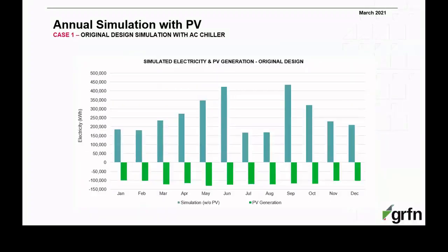If we compare the energy consumption versus the PV generation, we can see that, yes, the PV can generate a good amount of electricity, but it's almost half of the energy required by the building. So relying only on PV, and as we've seen here, we use most of the available space, and we use very efficient modules, we still cannot get to a net zero energy building. So it's very important to look at every single system that consumes energy in the building and find a way to reduce it in a cost-effective way.